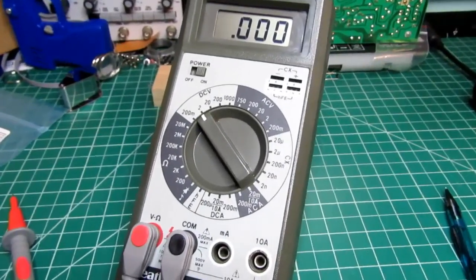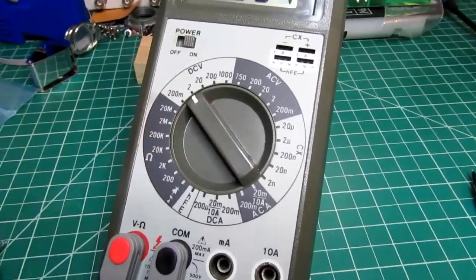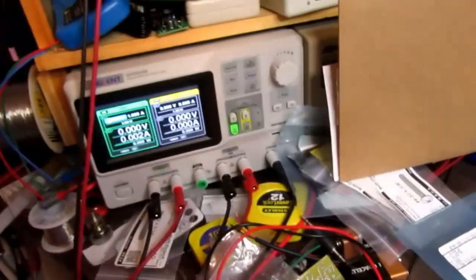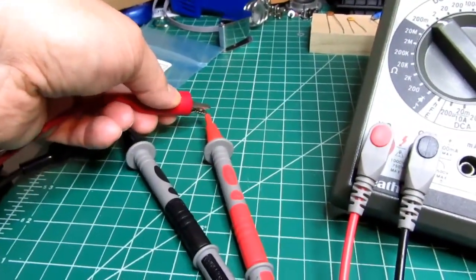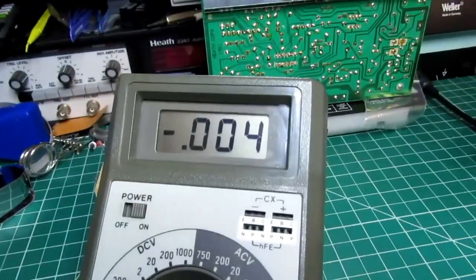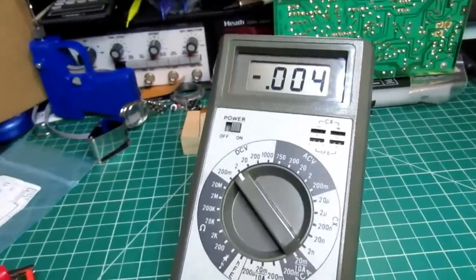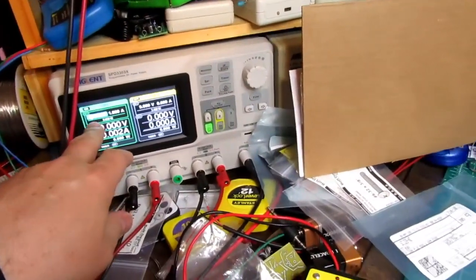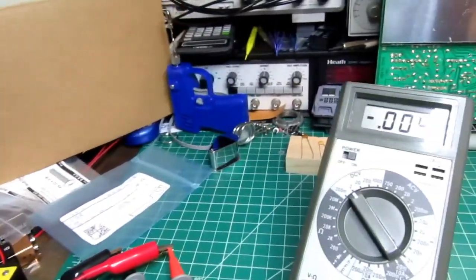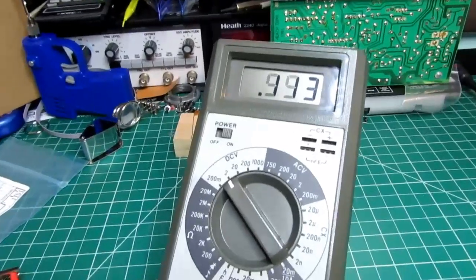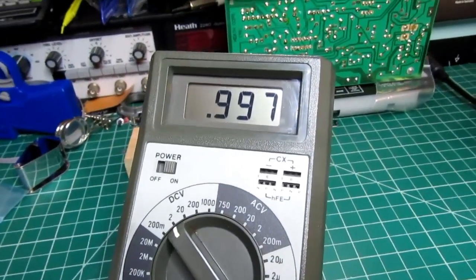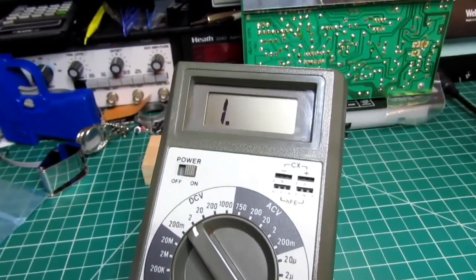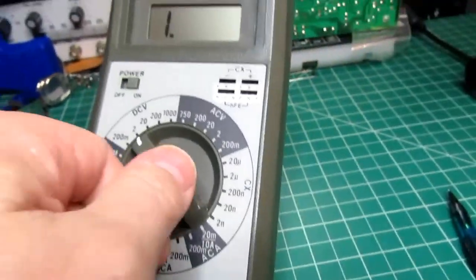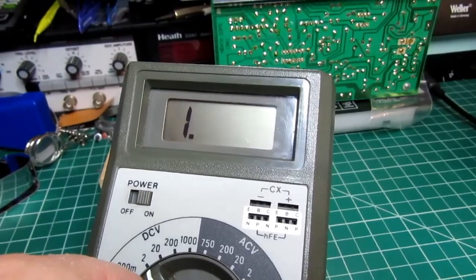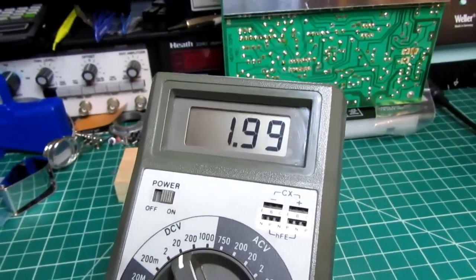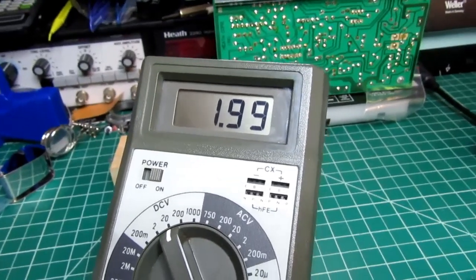Okay, let's start the demonstration with the DC volts. I'm not going to bother going down to the super low range. I'm just going to connect up my bench power supply to the test leads. And I've got a residual 0.004 volts hanging out there, with presumably 0 volts provided by the power supply. So I'm going to go up to 1 volt, and we're pretty close, 0.993. And we're over range because we're on the 2 volt range, so it just shows a 1 point for over range. So we select up to the 20 volt range, and I've got 1.99. Again, that's well within tolerance.